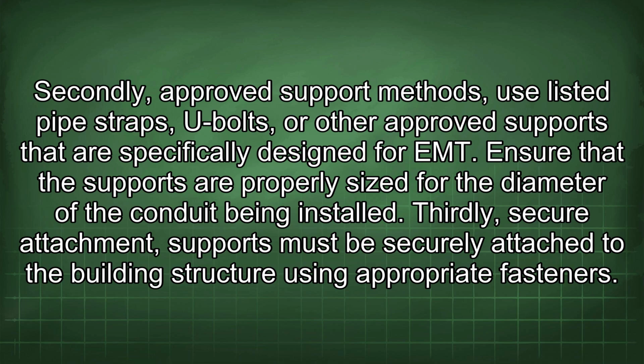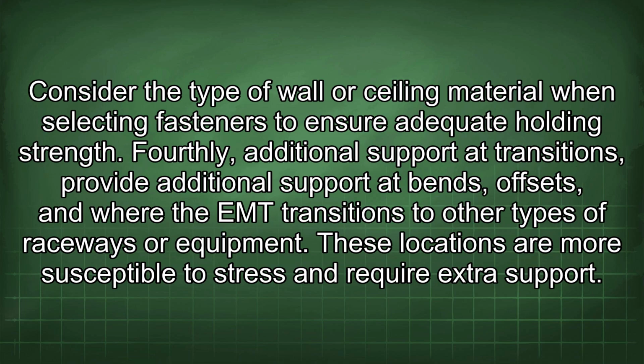Thirdly, secure attachment. Supports must be securely attached to the building structure using appropriate fasteners. Consider the type of wall or ceiling material when selecting fasteners to ensure adequate holding strength. Fourthly, additional support at transitions. Provide additional support at bends, offsets, and where the EMT transitions to other types of raceways or equipment. These locations are more susceptible to stress and require extra support.